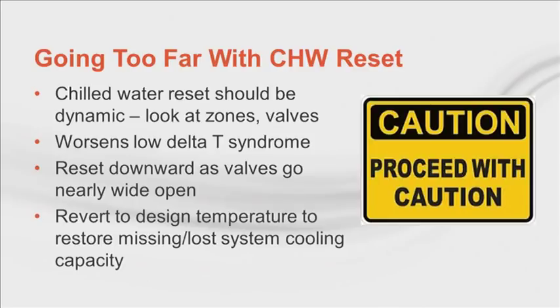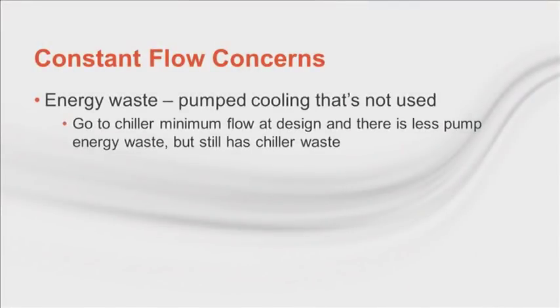And finally, chilled water reset gone awry shrinks the effective capacity of the chiller and should be removed when the chiller needs to be loaded further. The practical limitations of constant flow get more undesirable as the system gets bigger and has more chillers. The system creates and pumps cooling that is not used at part load conditions. As we've said before, if you're at chiller minimum flow all the time, it's just additional chiller energy. But most systems have pumping and chiller energy waste.